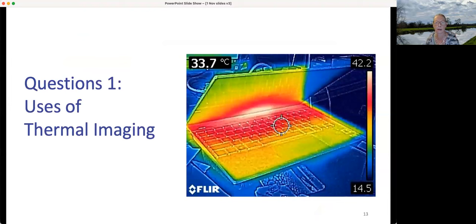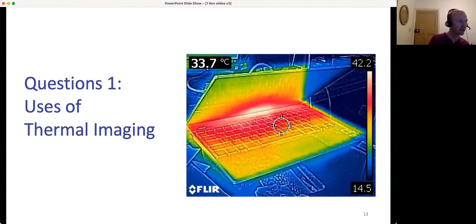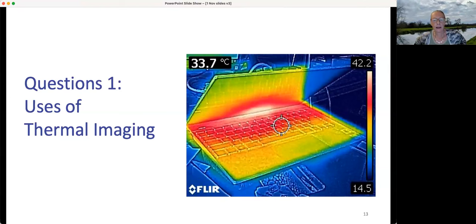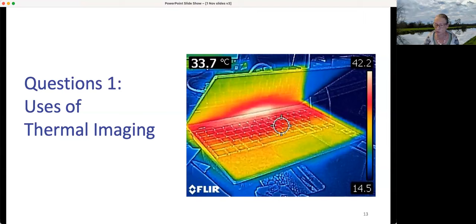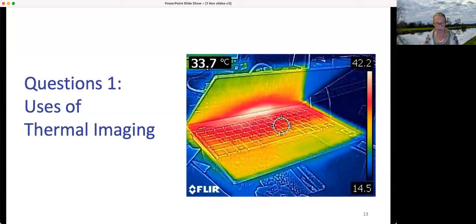There's a question: do you need to calibrate the camera? The cameras aren't calibrated very often, but if they look really off, you will. By and large you don't really mind, because you're looking at relative temperature differences. If you want to check camera calibration properly, you could put boiling water in a jug with some tape on it to see if it's reading nearly 100, and equally do iced water to see if it reads zero. But if it is causing a problem, you have to send them away to be calibrated — about £200.